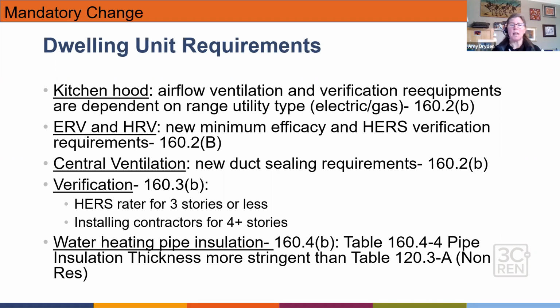We have some new minimum efficiency requirements for ERVs and HRVs and HERS verification requirements for the systems within multifamily. And for central ventilation, we have moved from prescriptive duct sealing to mandatory duct sealing requirements, 6%. And on verification, I want to call this out, this is again where we see some variances in number of stories. Where we are looking at verification of performance, whether duct leakage or quality insulation installation or any of those types of measures, kitchen range hood ventilation: if it's 3 stories or less, we're looking at HERS raters doing that verification. If it's 4 stories and above, we're looking at installing contractors doing the verification.